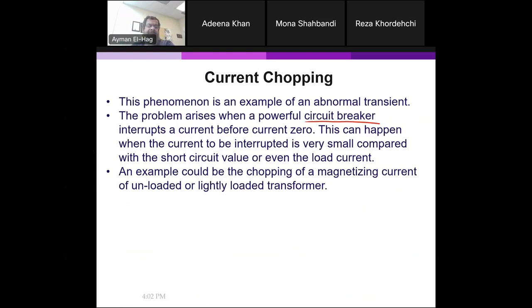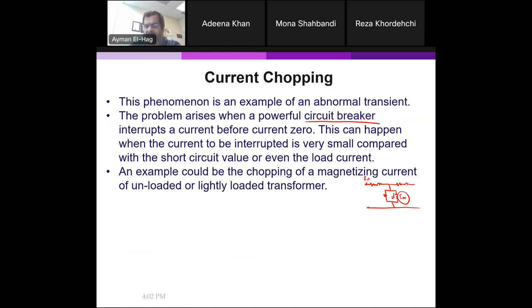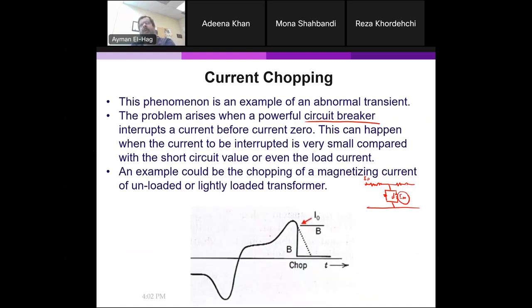For example, you have a transformer that is unloaded or lightly loaded, so you basically have the magnetization current. Looking at the transformer: this is the primary circuit, this is the core, and here is the secondary. The transformer is at no load — open circuit or very lightly loaded. So the main current in the primary is the magnetization current. This is a typical no-load current, filled with third harmonics because the core inductance is due to the BH curve — it is a nonlinear inductor, so the current itself is nonlinear.